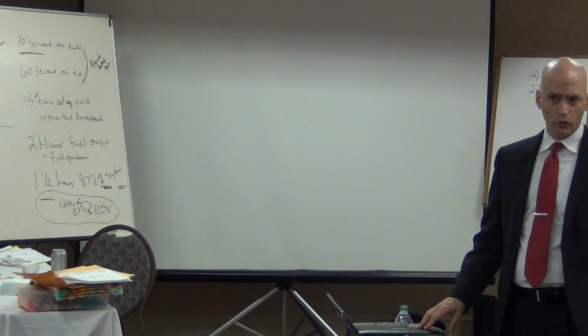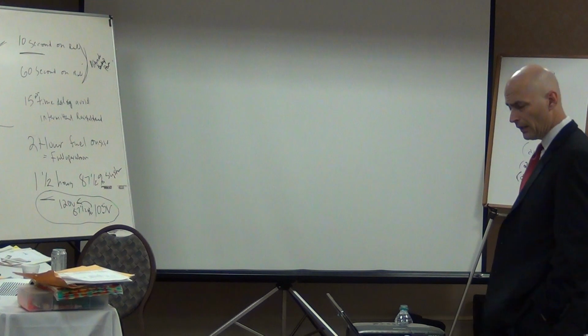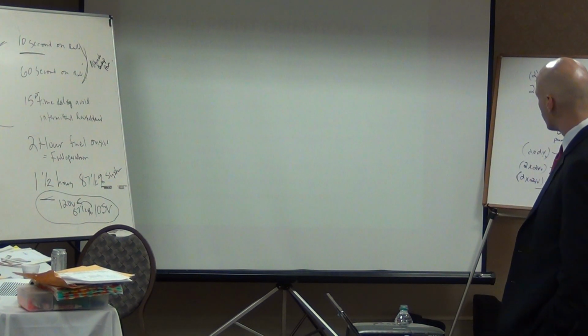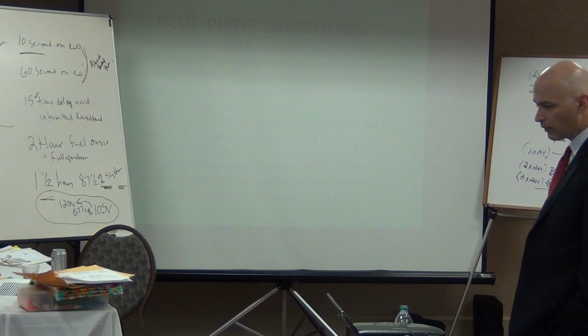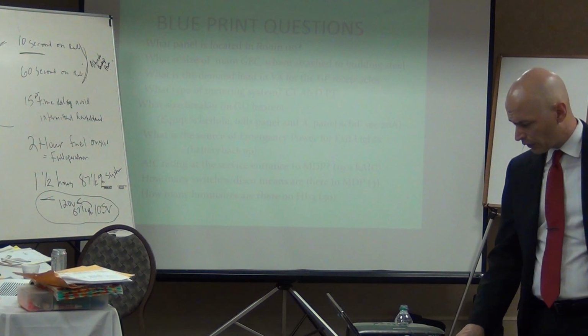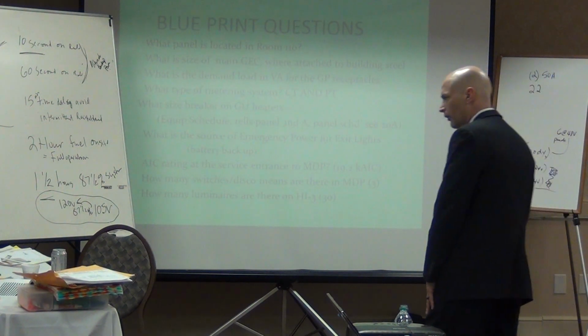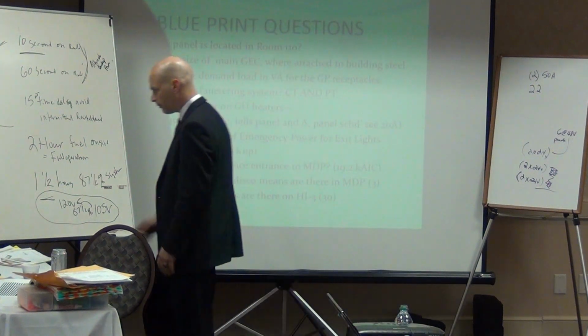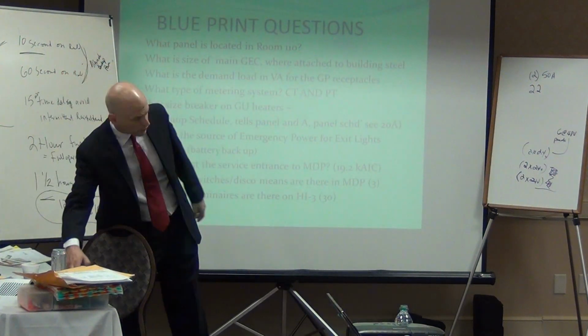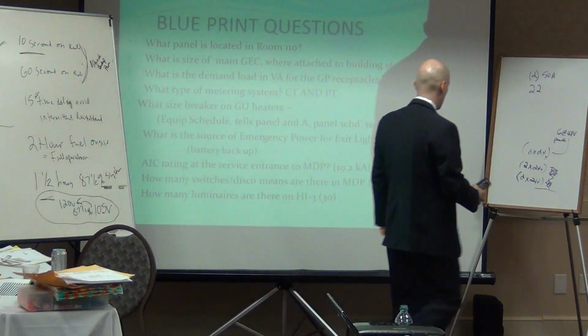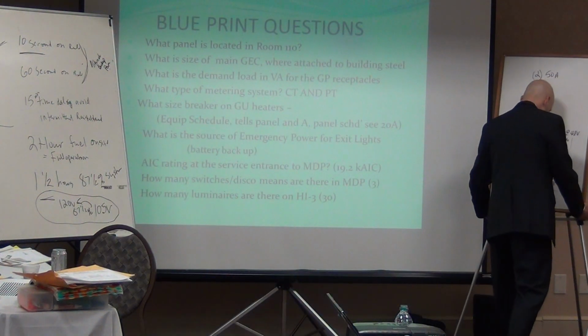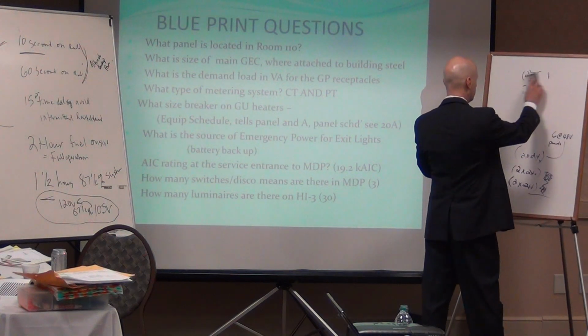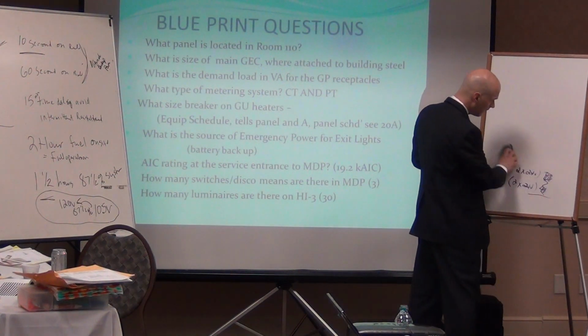So L1C is the panel located in the room, and the conductors that feed it are number 8, number 10 ground. This is kind of the same stuff I've got in your book, so I'll just put them in there so you won't have to write as much. But the size for the main and the grounding electrode conductor, those two terms, guys, you've really got to keep very clear in your mind. They're two distinct animals, and a lot of times people get confused with the terms ground, grounding, and grounded.